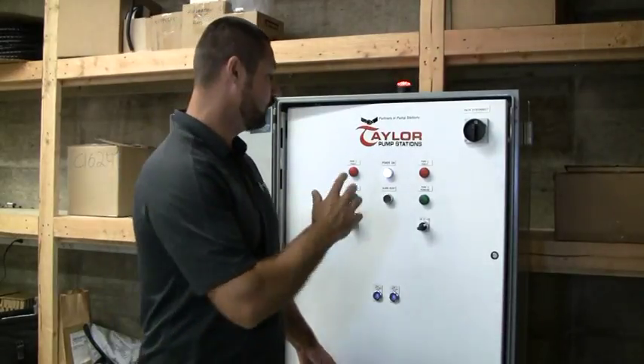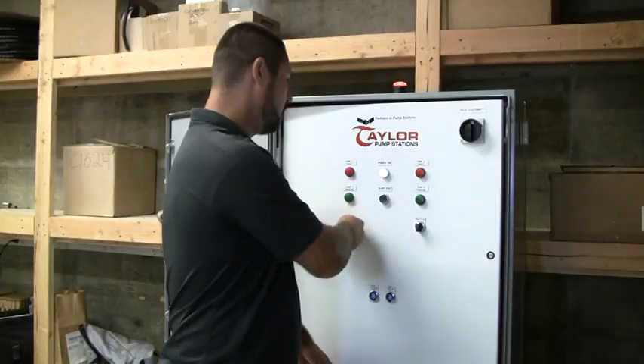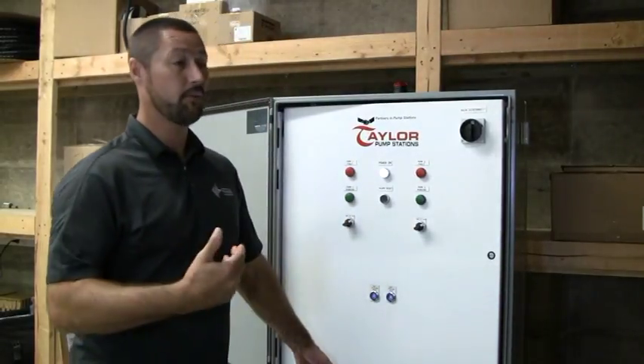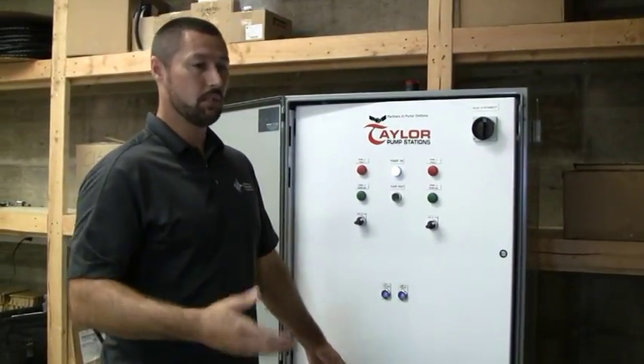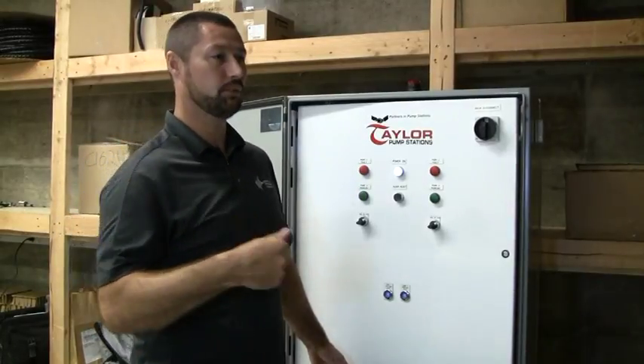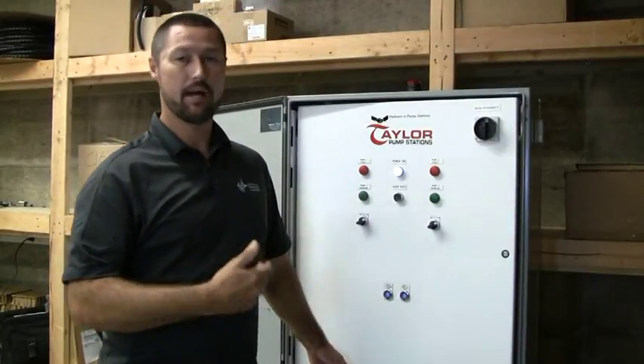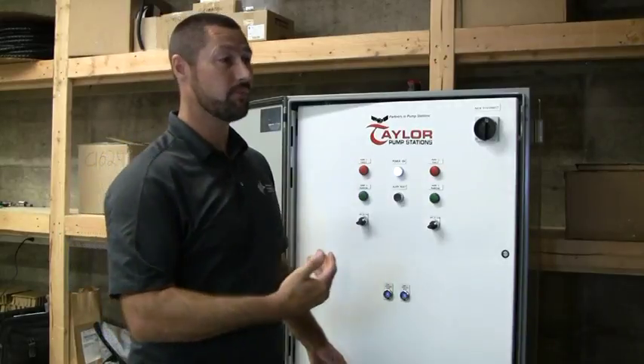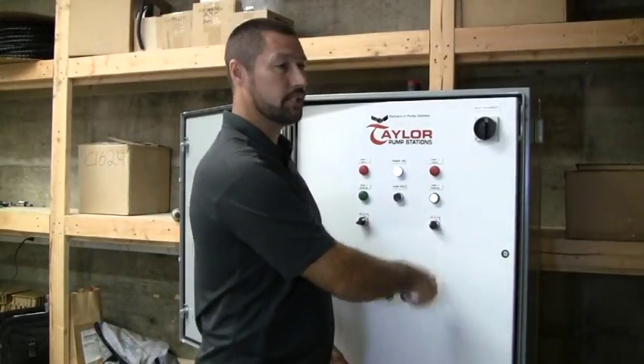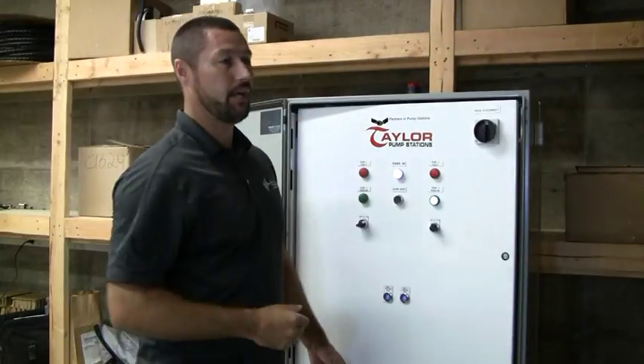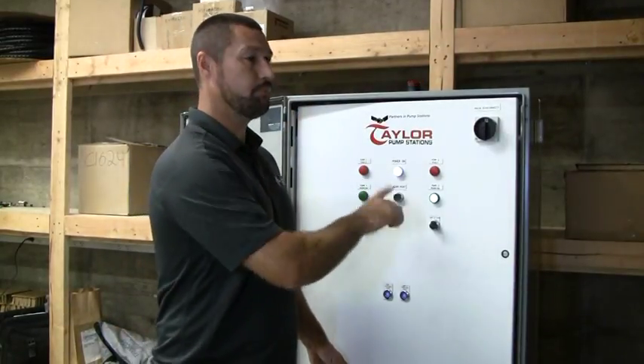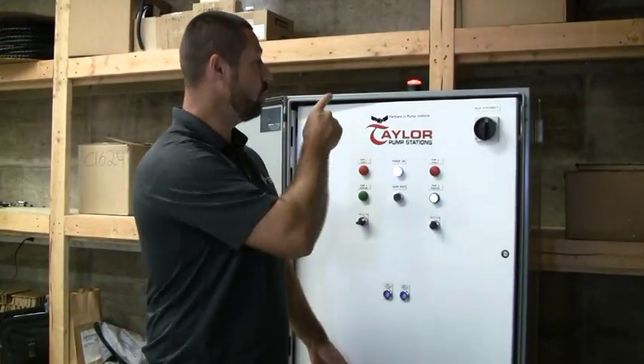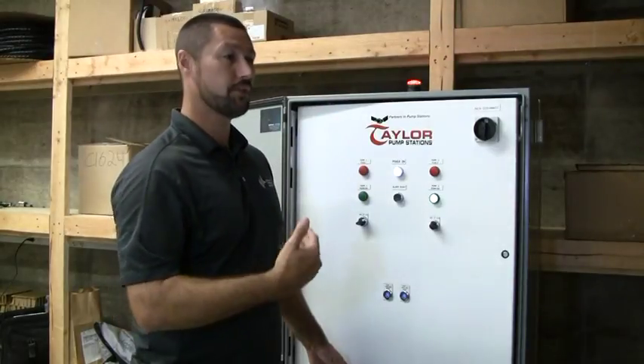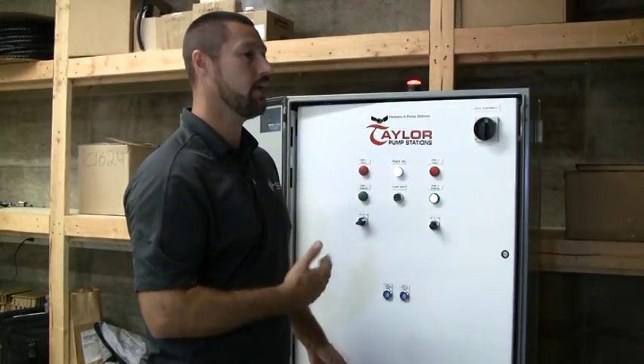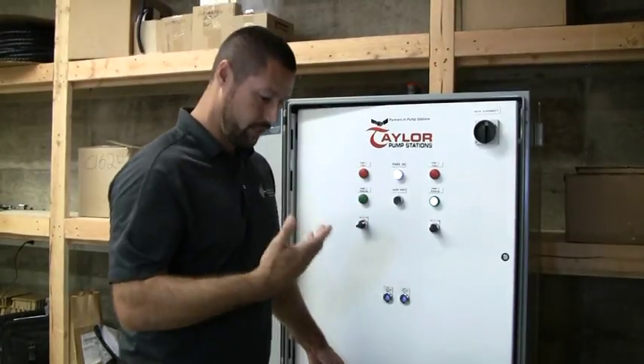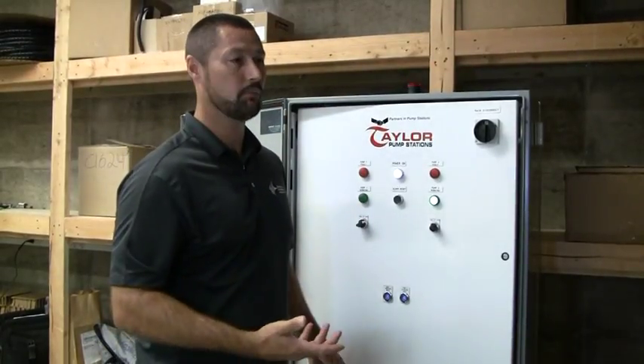So in addition to that, we've had municipalities say, hey, we need to pump this station down. Well, we've seen them pull floats out of the water, we've seen them push on transmitters, we've seen them bypass those safeties. So what we have in play, in our hand-off-auto section, is that it's going to flash and it's going to tell you that, hey, you can put me in hand, but please don't leave me here. There's other safeties in the program that come into play after that, but this is something where they can physically pump it down, they can see what's going on down below in the wet well.